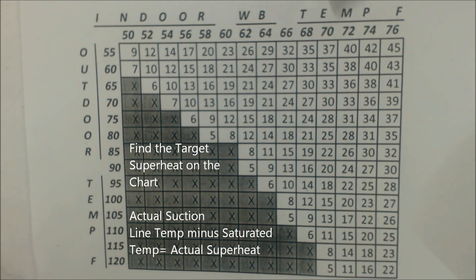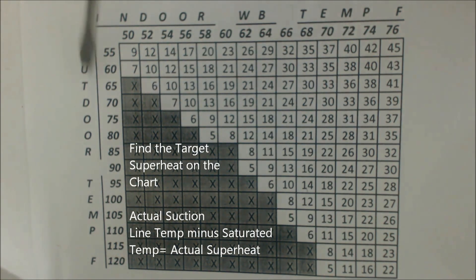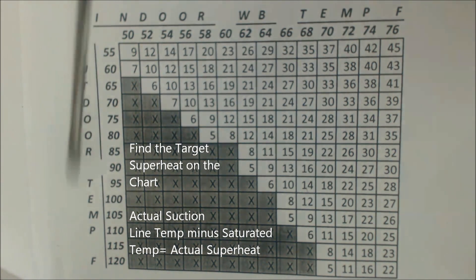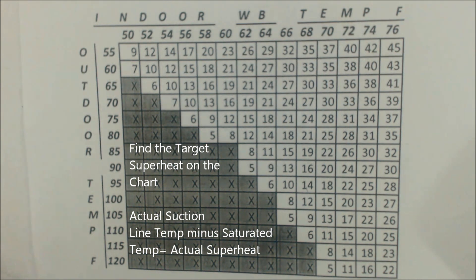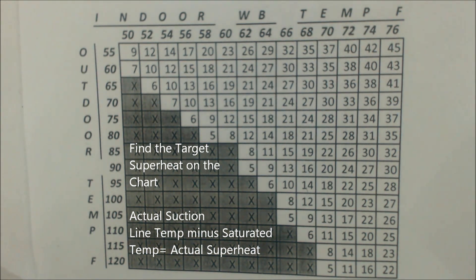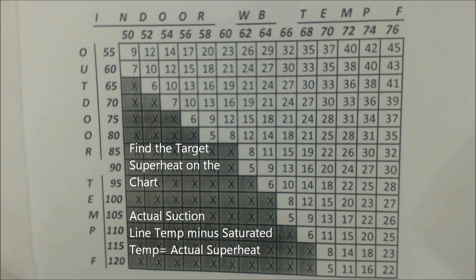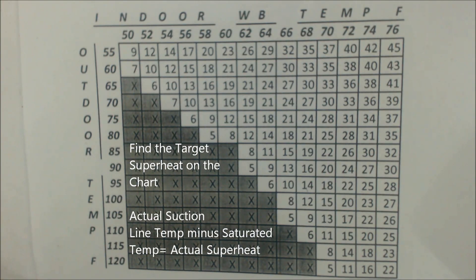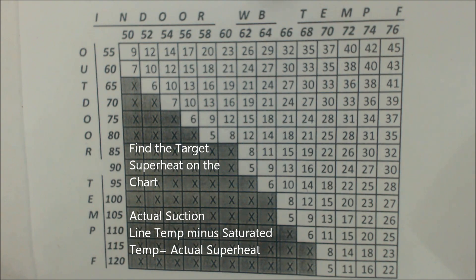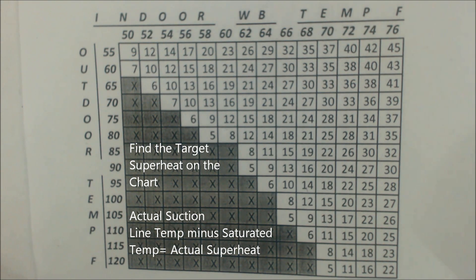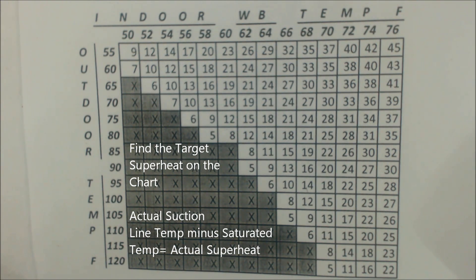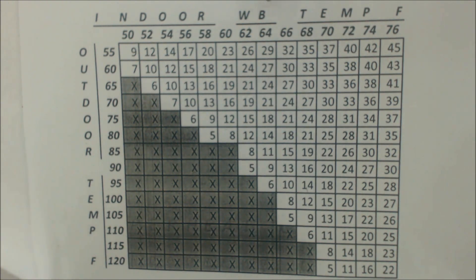We're going to be doing some superheat charging chart drills. We're going to take the outdoor temperature, which is the outdoor entering air temp on the condenser coil, maybe about six inches away from the condenser coil, out of the sun, down low, not where the heat's blowing out at, rejecting it out of the top of the outdoor unit. Then you're going to take your indoor wet bulb temperature at your largest return grill in the house with your psychrometer, whether that's a sling psychrometer or a digital psychrometer.